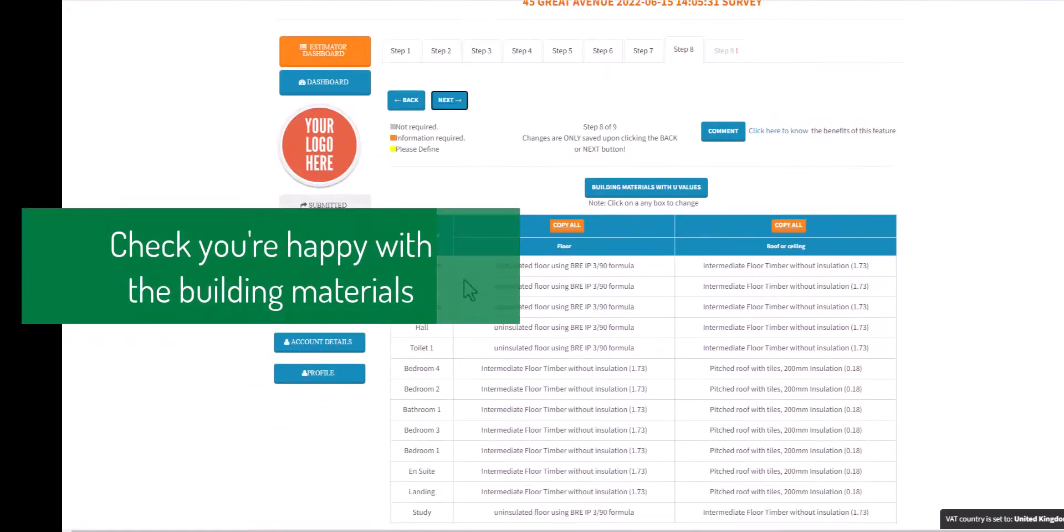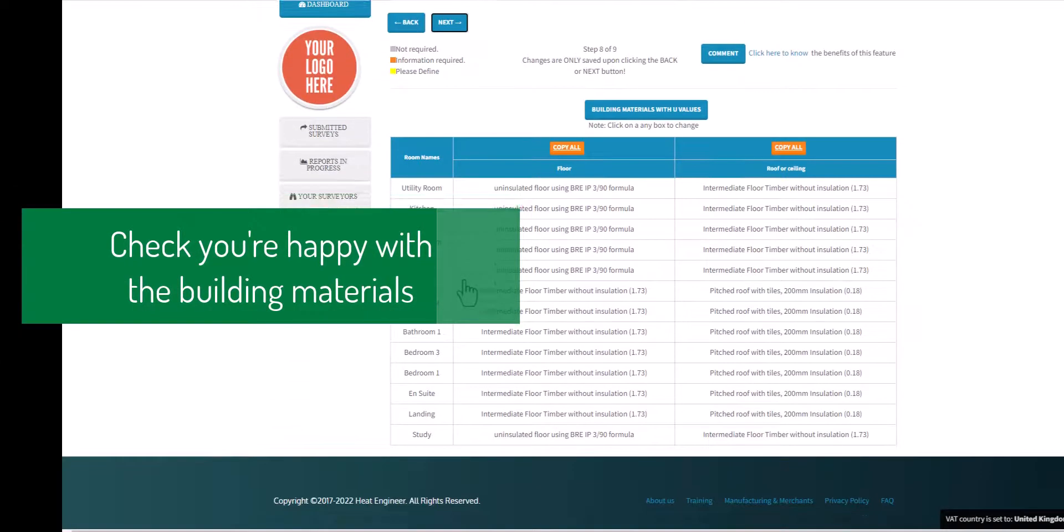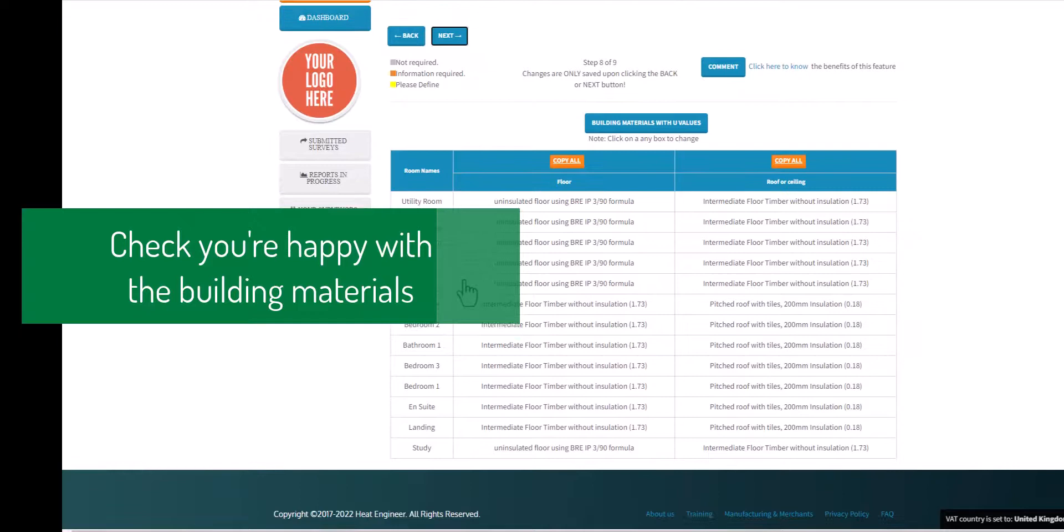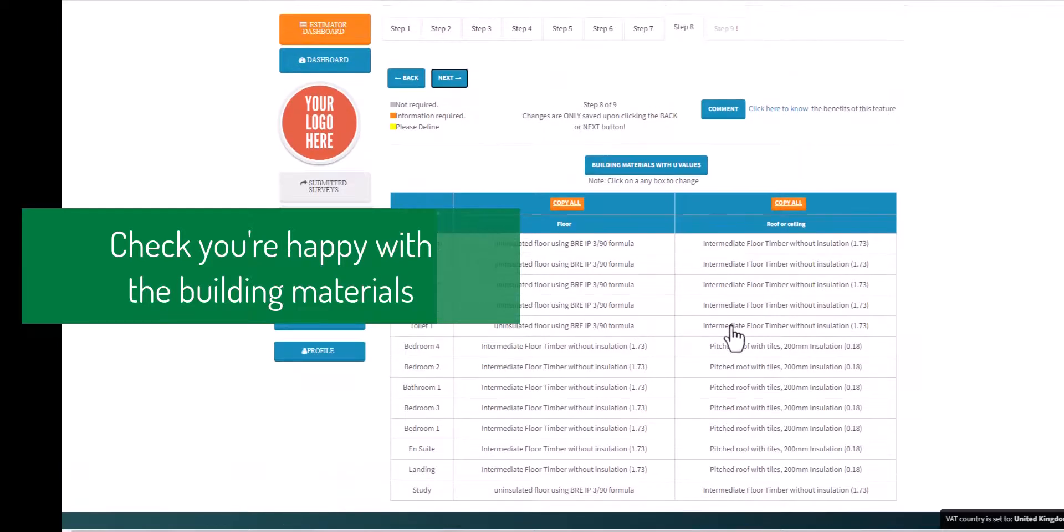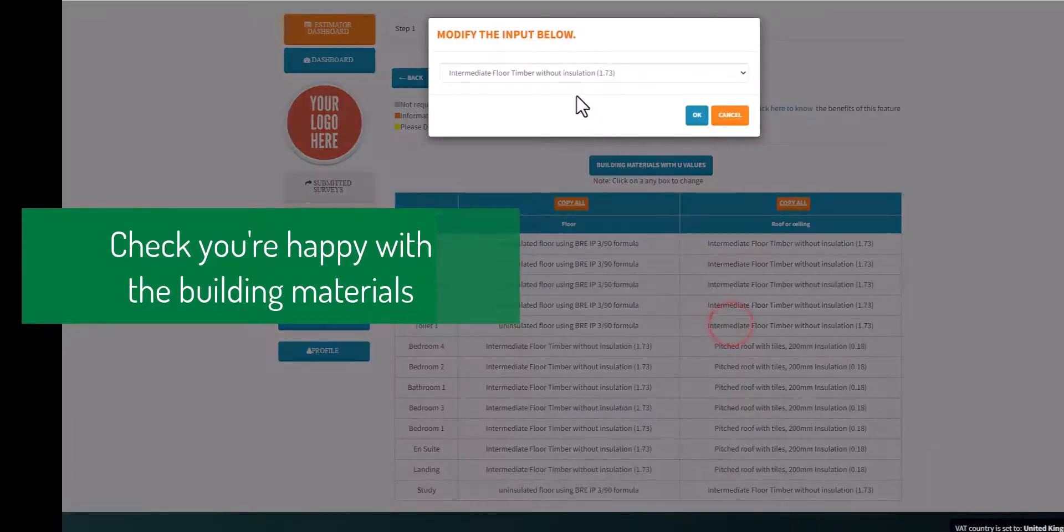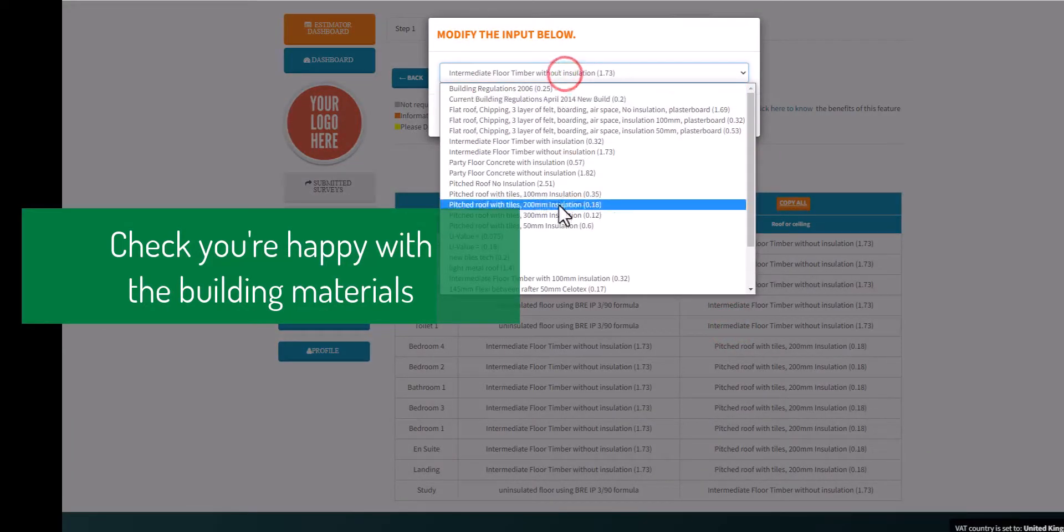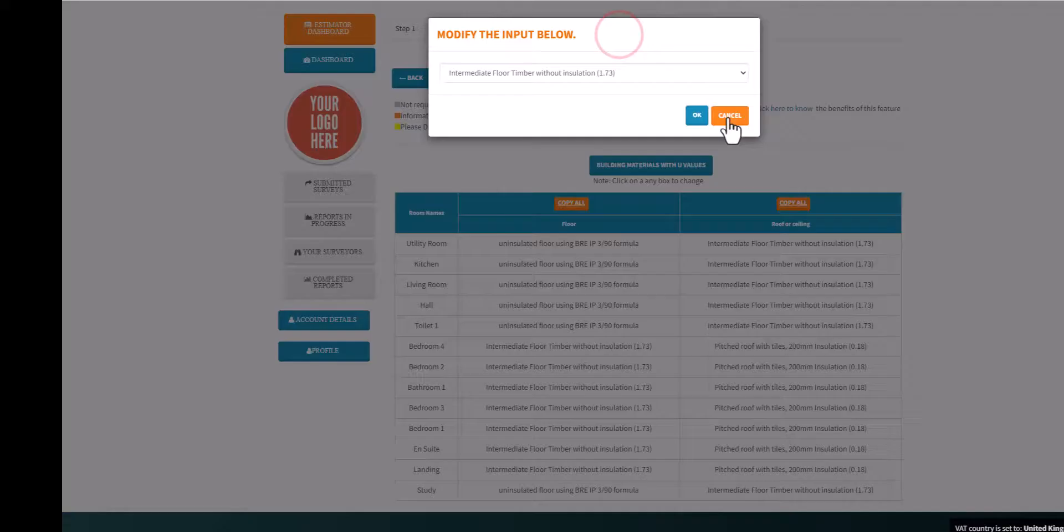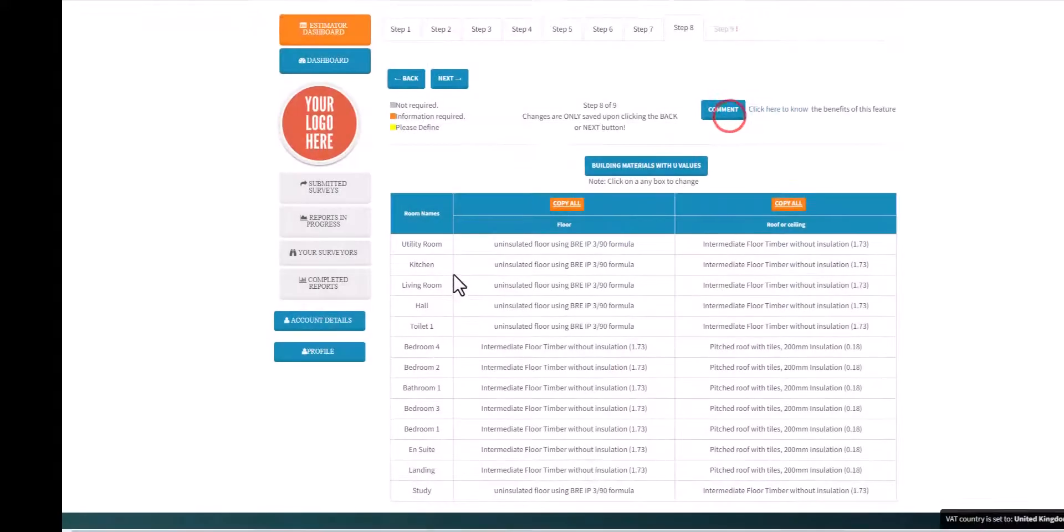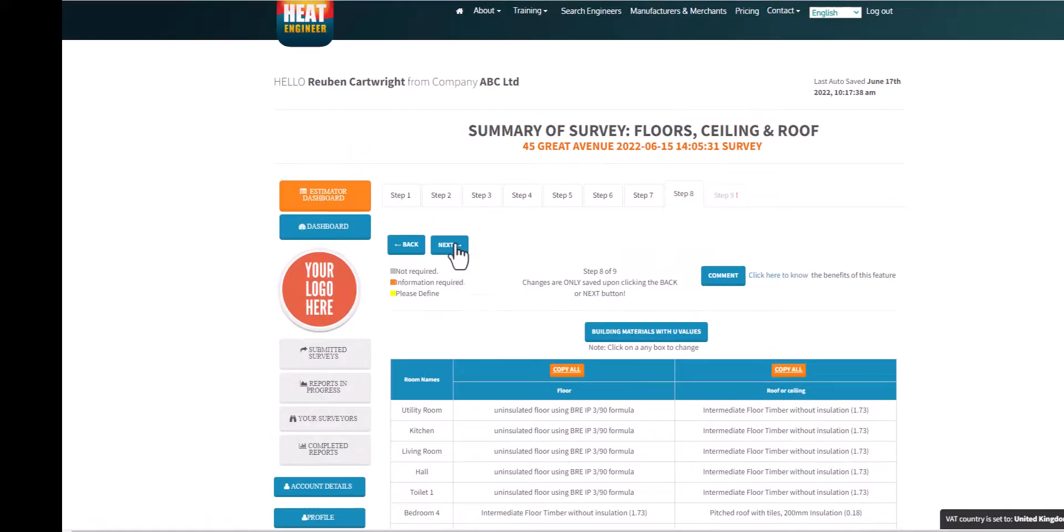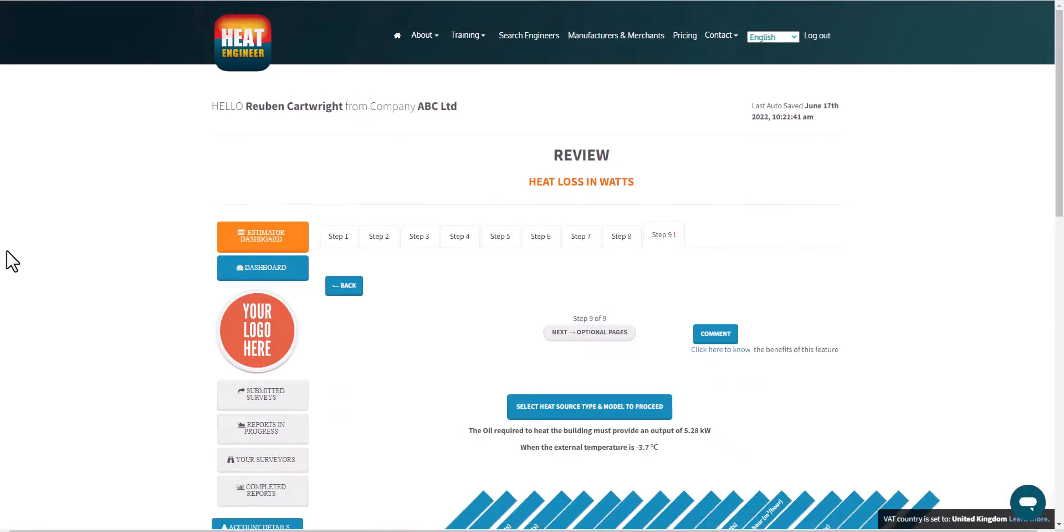You can at any step also work out U-value as well for a custom defined building material and then add that in there, but most of this information in this case has been typed in via the site survey within the app.